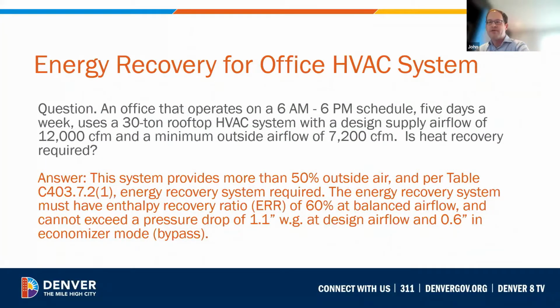Note that since energy recovery is required, the fan system can take a pressure drop allowance when calculating fan power and comparing against the requirements in section C403.8.1 of the Denver Energy Code. So this is just an example of a system that would require energy recovery for the prescriptive tables that we had just reviewed.